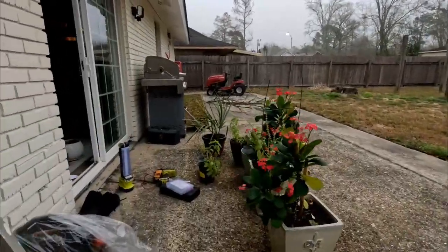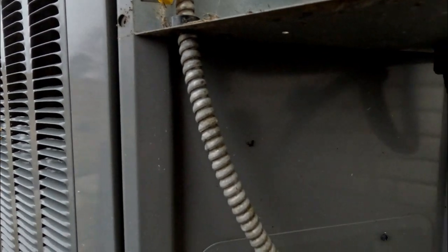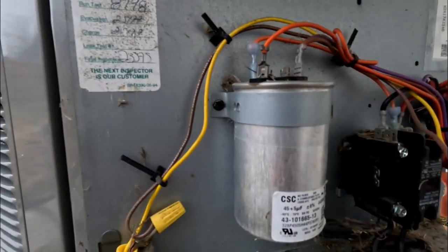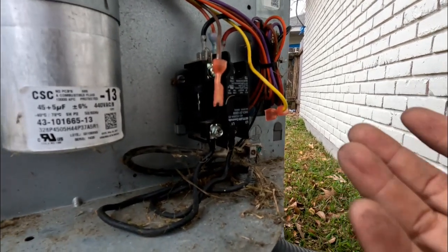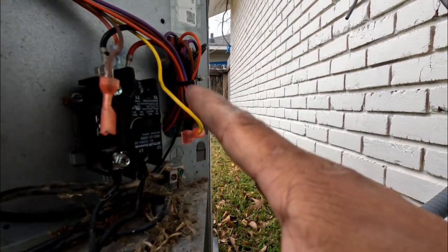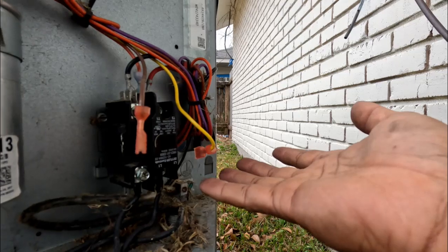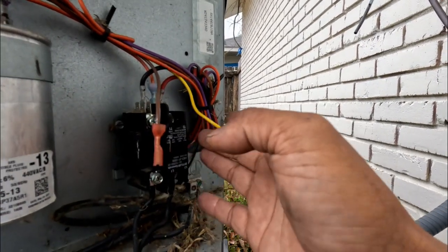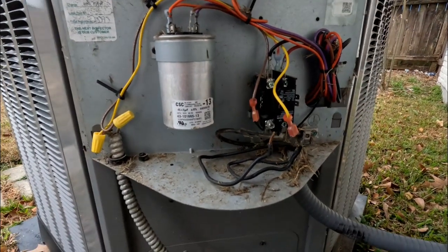Always check to make sure you don't have power coming through - because if it does, my wife's going to be crying. We have no 240 volt - confirmed. We need to remove all this. Basically we remove the screws, take the old contactor out, and put the new one in. This is called a one-pole contactor - power continues through this tool side but there's no power through this side. A two-pole contactor has two sets of contacts connected together.